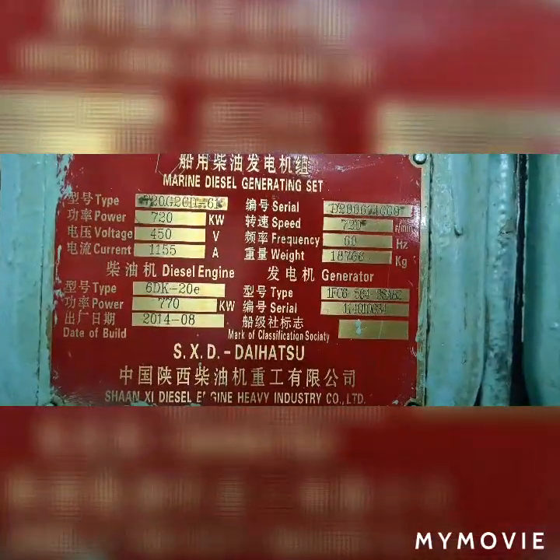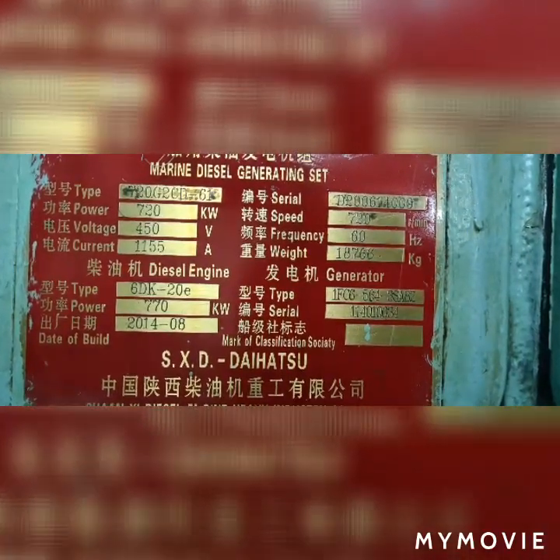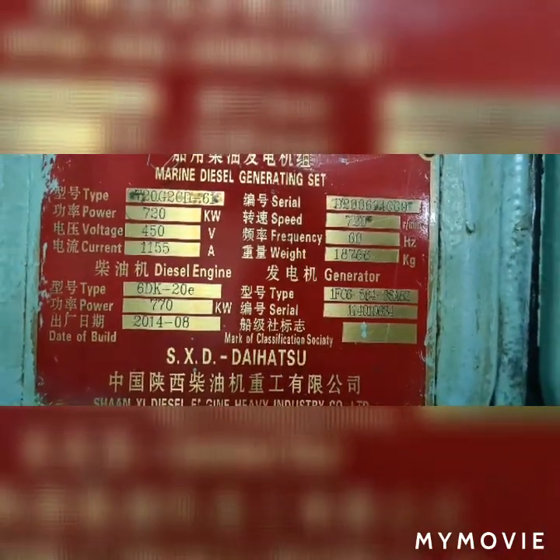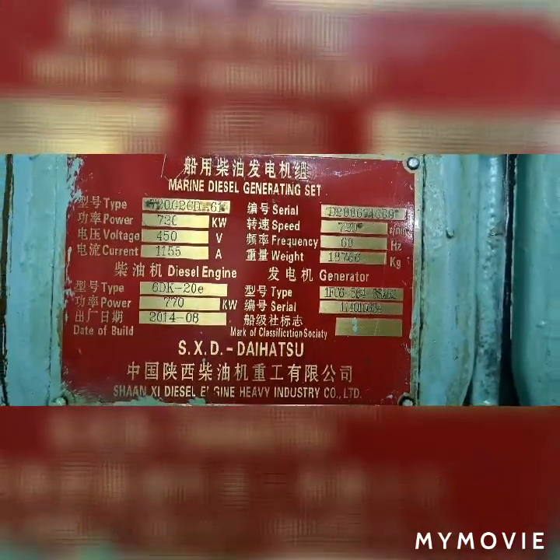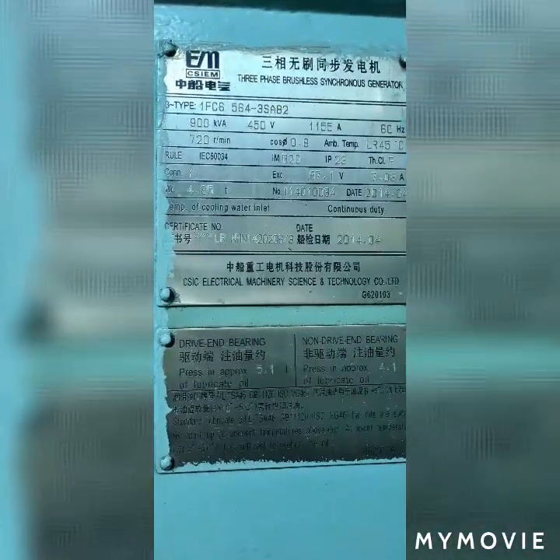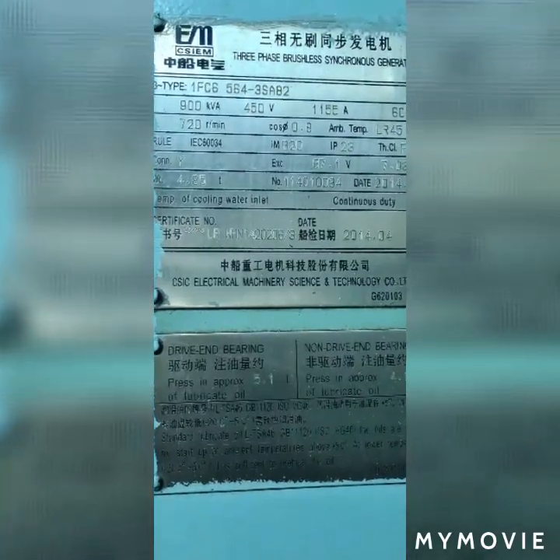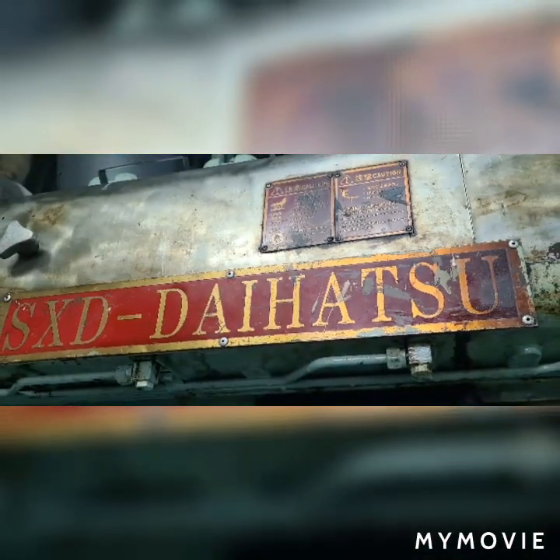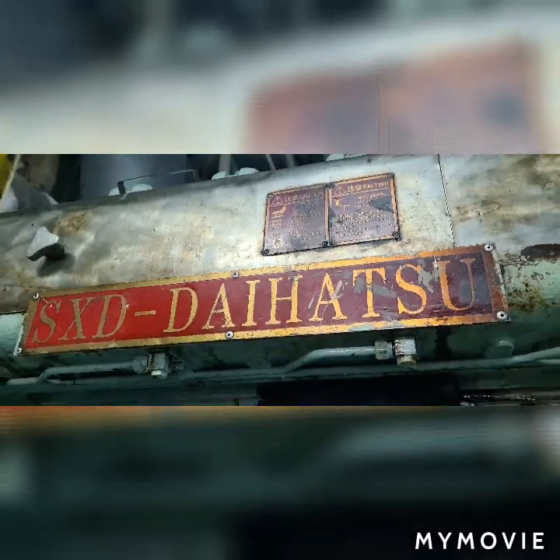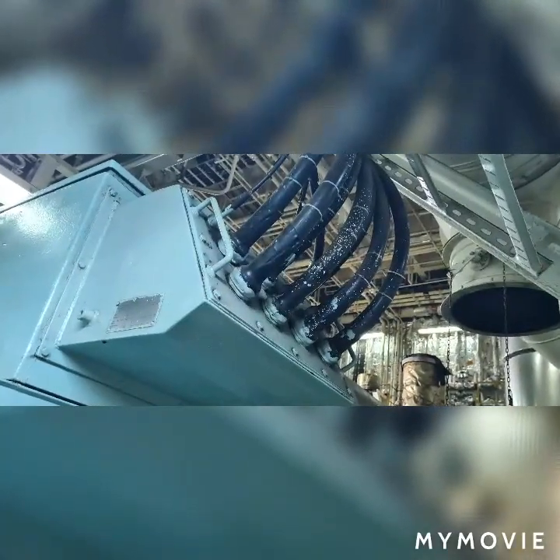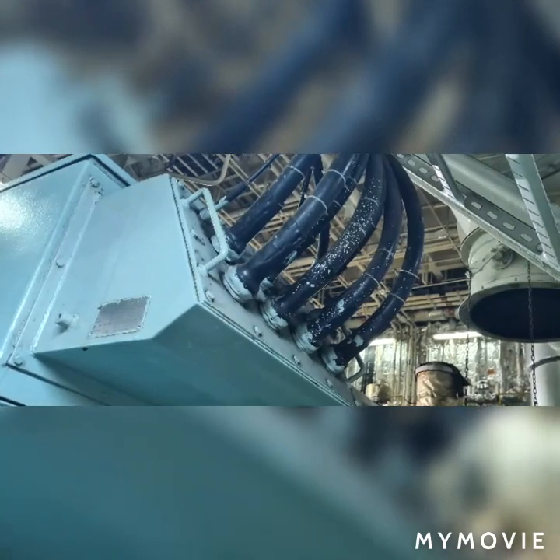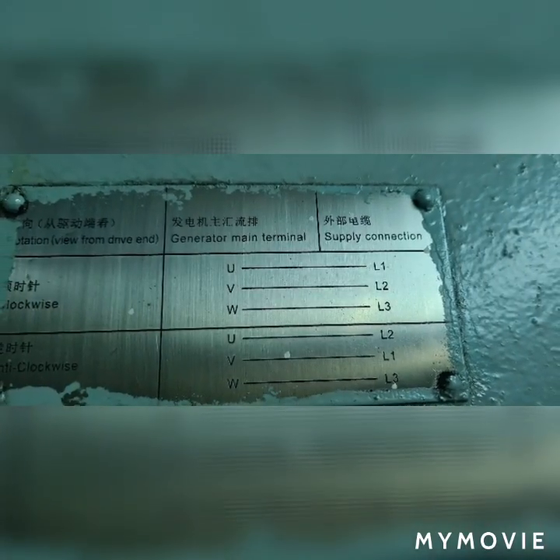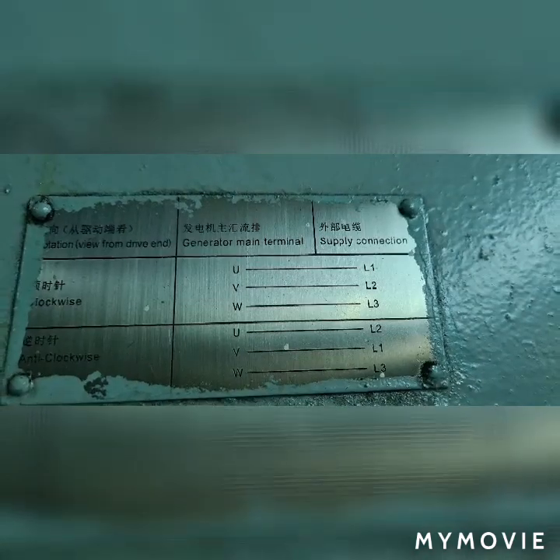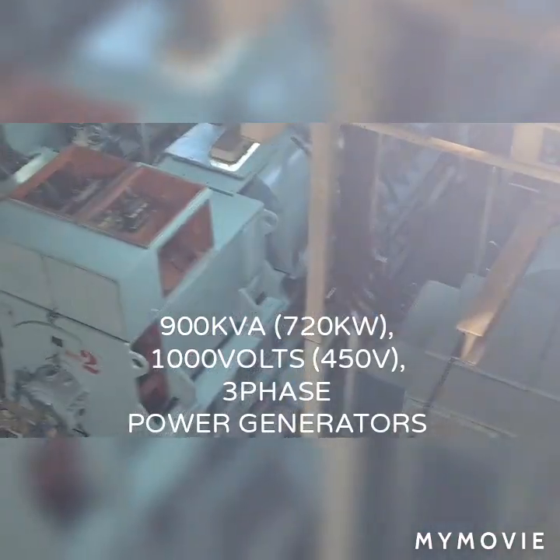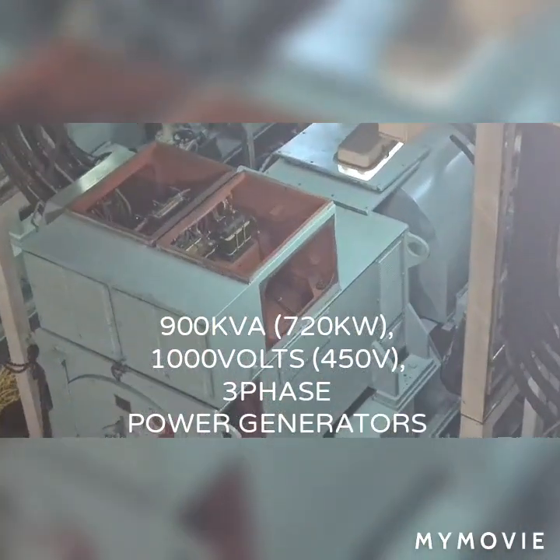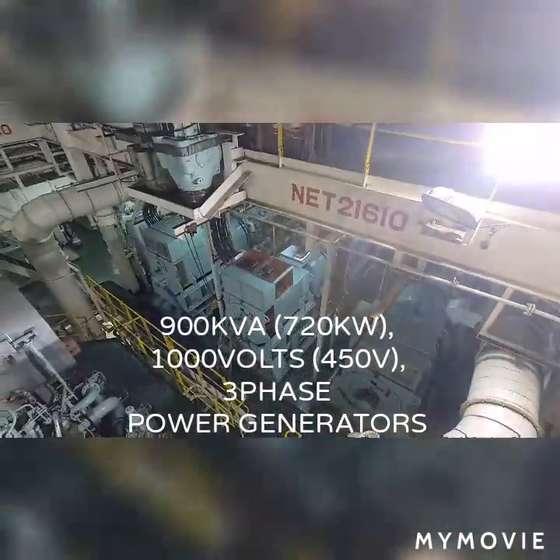Okay, this is the generator nameplate ratings, and I have here 720 kilowatts, 450 volts, 900 kVA, and this generator has an engine driven made by SXD Daihatsu. This is the power cable that I have, and down there is a power generator 1, 2, and 3, from which I'm going to do some maintenance, inspection, checks, and Megger insulation tests.